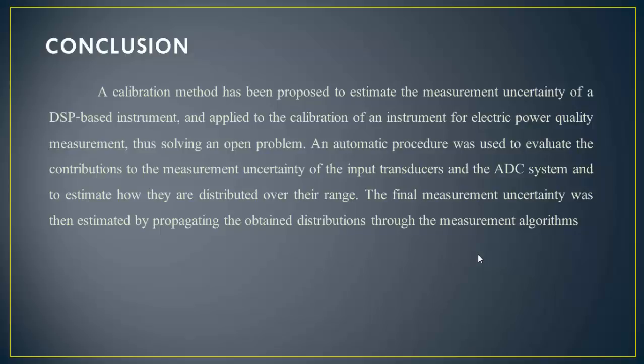Conclusion: A calibration method has been proposed to estimate the measurement uncertainty of a DSP-based instrument and applied to the calibration of an instrument for electric power quality measurement, thus solving an open problem. An automatic procedure was used to evaluate the contribution to the measurement uncertainty of the input transducers and the ADC system, and to estimate how they are distributed over their range. The final measurement uncertainty was then estimated by propagating that obtained distribution through the measurement algorithm.